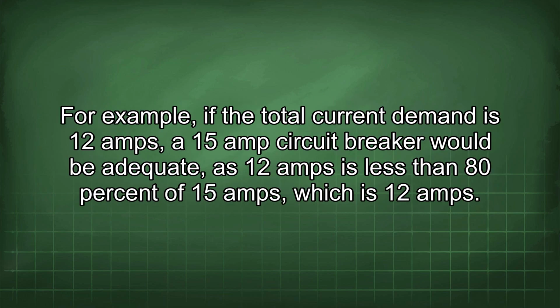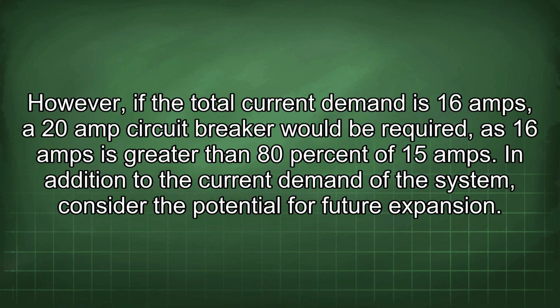For example, if the total current demand is 12 amps, a 15-amp circuit breaker would be adequate, as 12 amps is less than 80% of 15 amps, which is 12 amps. However, if the total current demand is 16 amps, a 20-amp circuit breaker would be required, as 16 amps is greater than 80% of 15 amps.